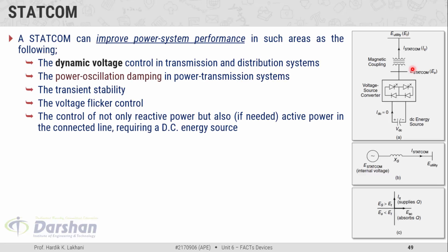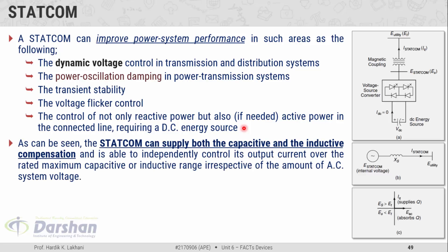Key features of STATCOM: A STATCOM can improve power system performance in many areas — dynamic voltage control in transmission and distribution systems, power oscillation damping in power transmission systems, better transient stability, and control of voltage flickering. It does not only control reactive power, but also active power in the connected line when a DC energy source is present.